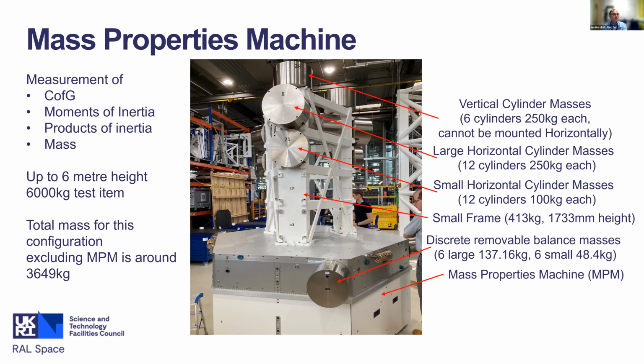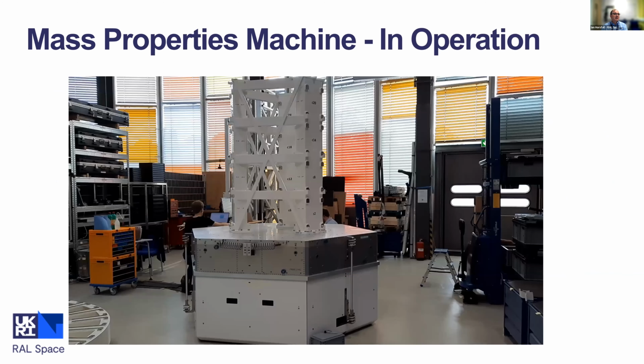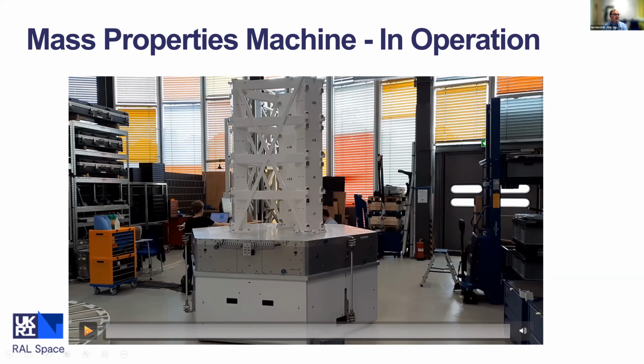I'll show you a video of this machine operating now. With Zoom video rates being the way it is, you've got to look quite carefully. What I'll do is start the video, and we're going to zoom in on this position here, just where the support base of the machine and the moving platform match. When we zoom in, you may be able to see it's moving backwards and forwards around 5 millimeters. This is a typical displacement during the test. So the test item sees an acceleration of a very small fraction of 1g during the test, and just sits there and oscillates slightly whilst data is collected and deconvoluted. So I'll start this running now.